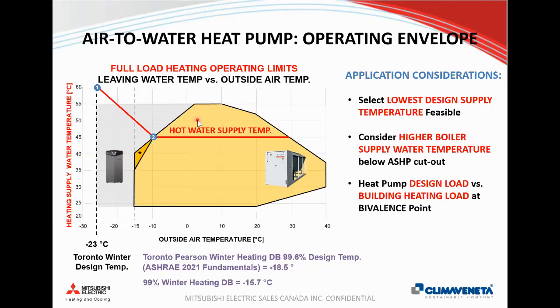according to the operating envelope, or if you look at a manufacturer's brochure, it's also important to distinguish standard AHRI conditions versus application conditions. So if you look at our catalog, it'll say hot water as high as 55 degrees Celsius, which is true. But whenever you look at the operating envelope, you'll see that the relationship between supply temperature versus outside air temperature will decrease below 3 degrees.